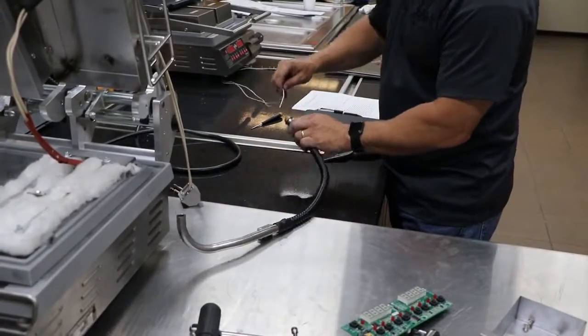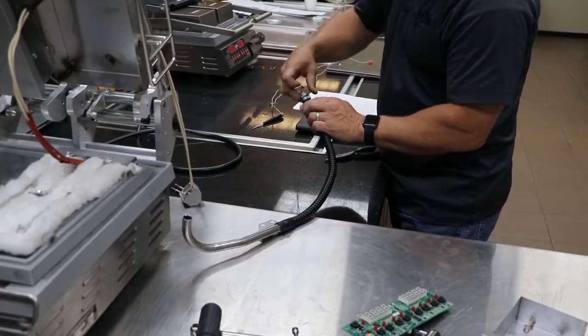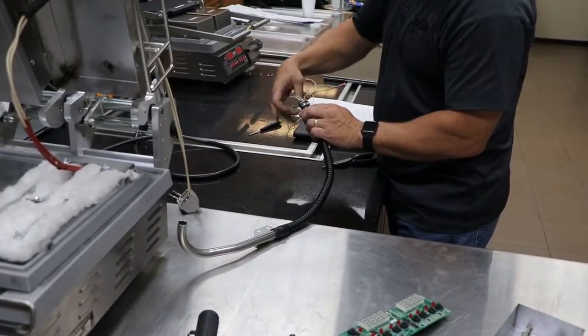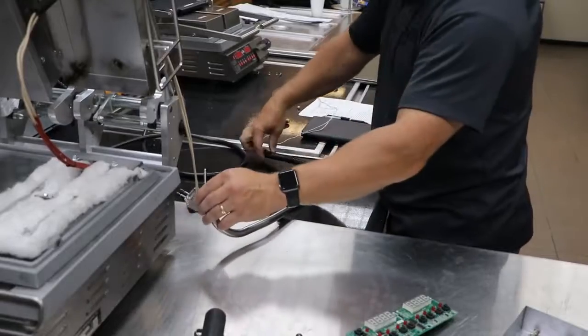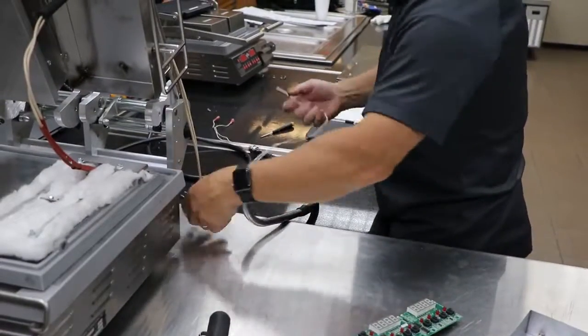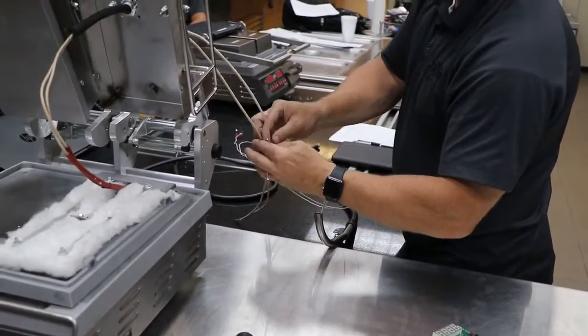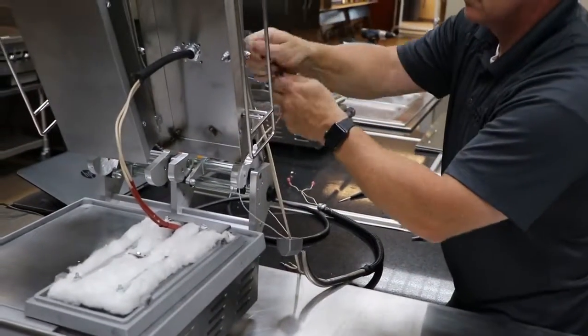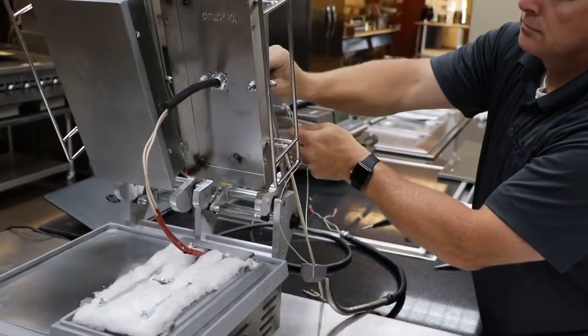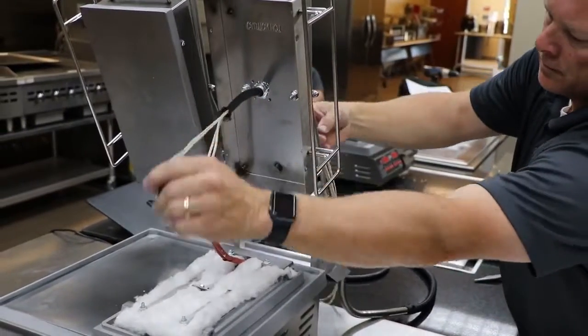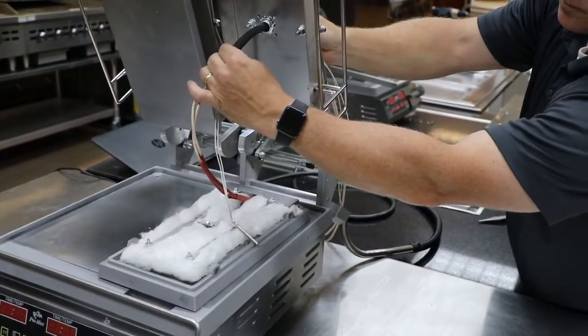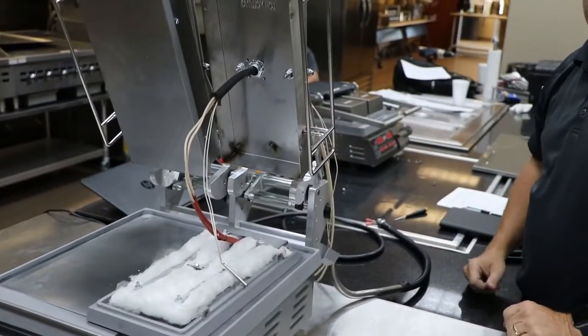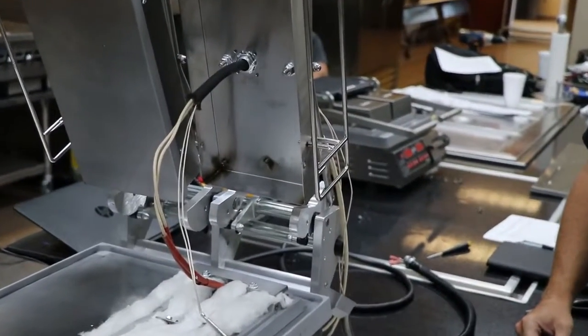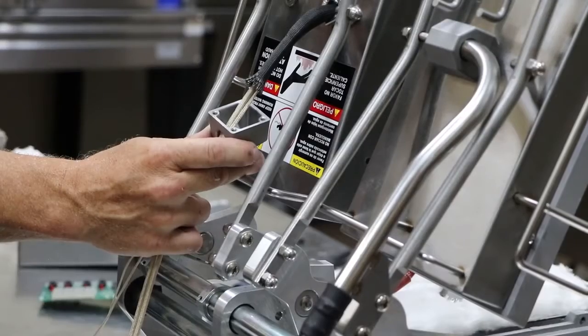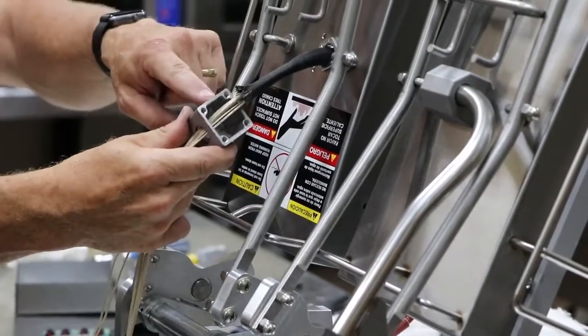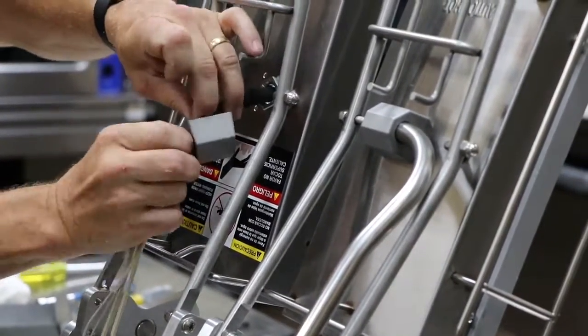Feed the new probe through the conduit assembly, probe end first, into the sleeving, through the top housing block, and into the top housing. Verify sleeving is protruding a minimum of 1 inch from inside the top housing and out of the top housing block. Reattach the top housing block using the 4 Phillips head screws previously removed.